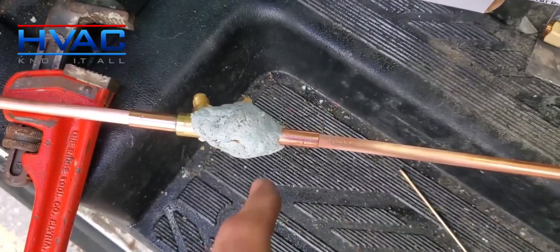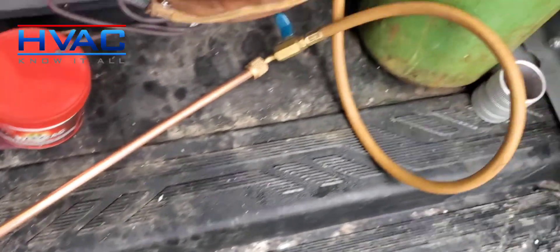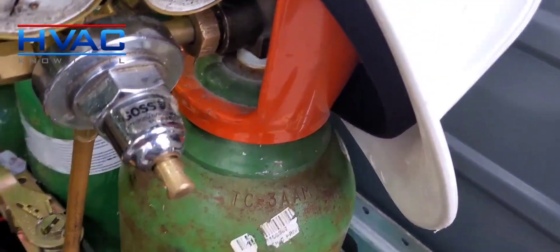I have it all ready to go. Wet rag on there for protection, and I've also taken out the sensitive parts — there's a little Teflon O-ring that I've taken out as well. So we can braze that up, and I have my nitrogen. We're just going to flow a little bit of nitrogen through that while I braze it up.